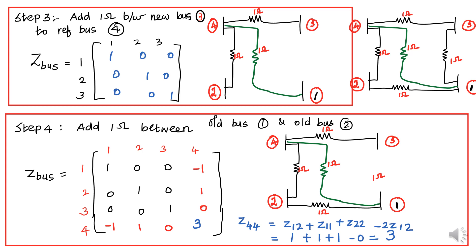Next, step number 3: Add 1 ohm between new bus 3 and reference bus 4. Here the order of the matrix is increased by 1, giving a 3x3 matrix with labels 1, 2, 3. Already we have Z(1,1) and Z(2,2). Now fill Z(3,3) = 1. Is there any connection between buses 3 and 1, 3 and 2? No. There is no connection between buses 1 and 2, 3 and 1, or 3 and 2. So all remaining off-diagonal elements are simply 0. This is the new matrix obtained from step number 3.